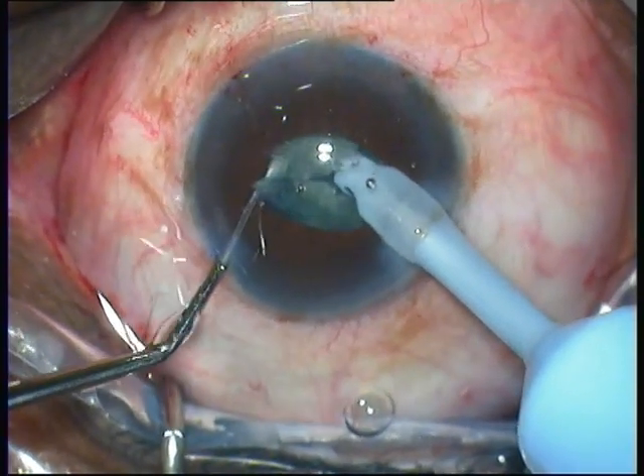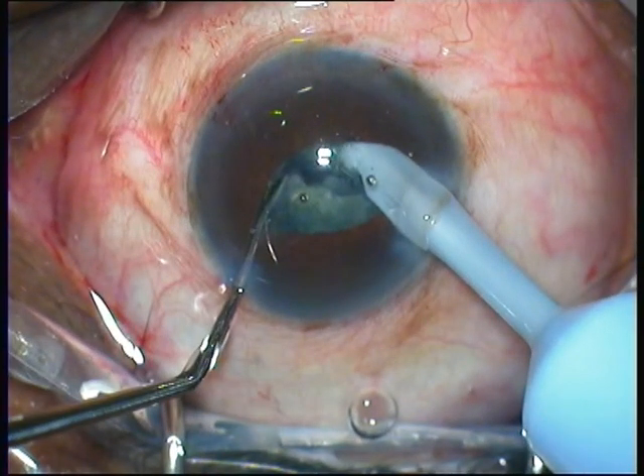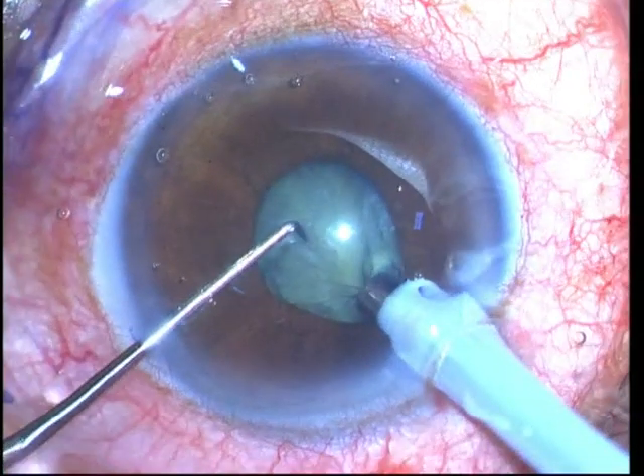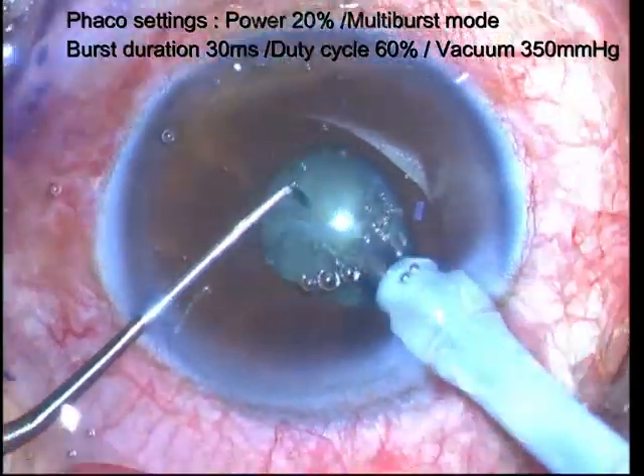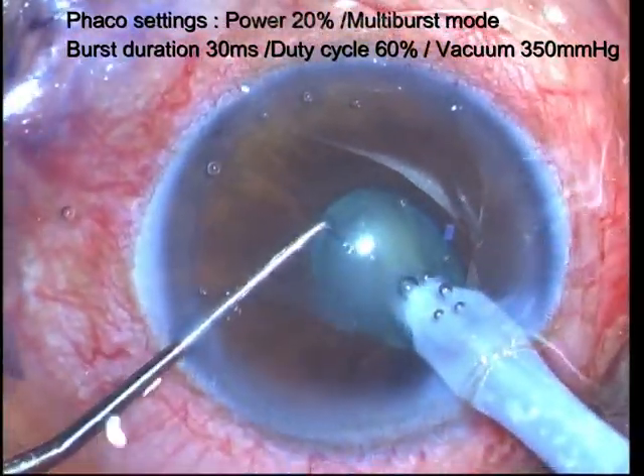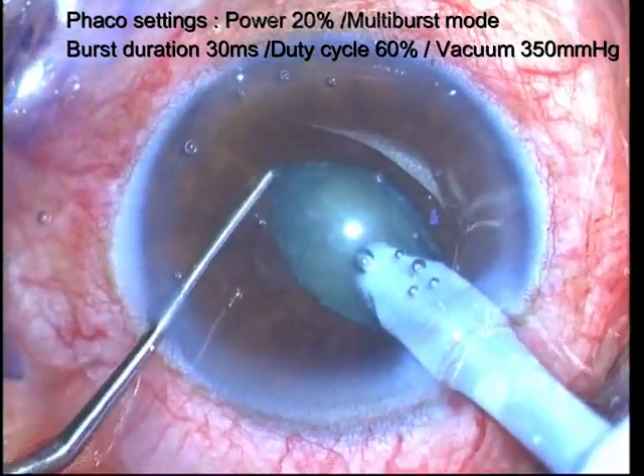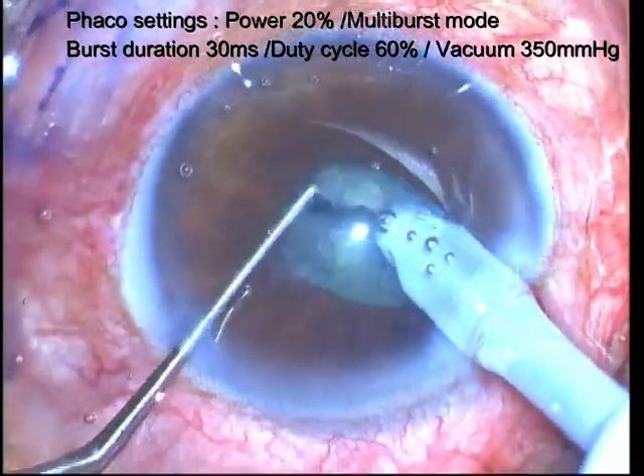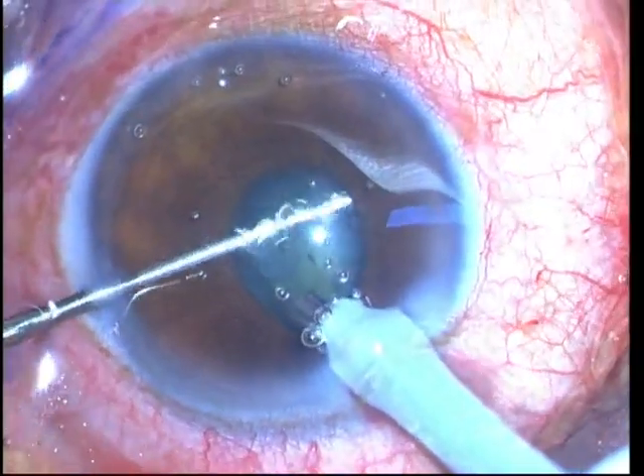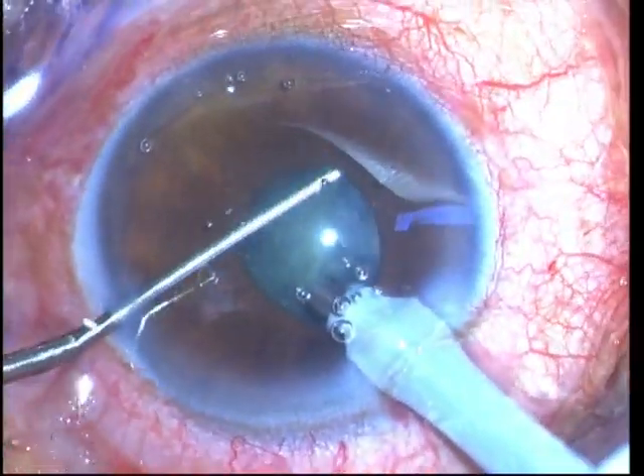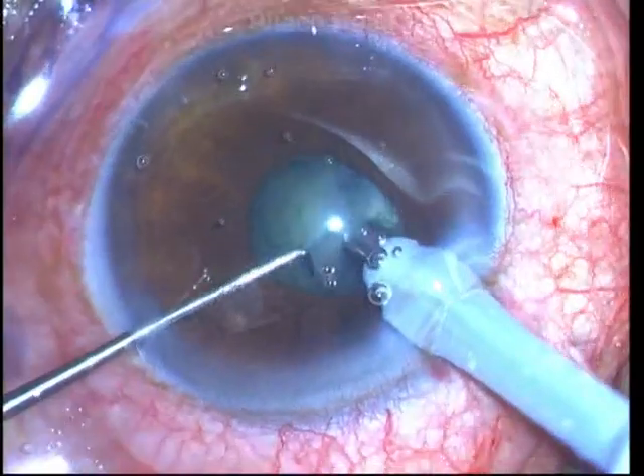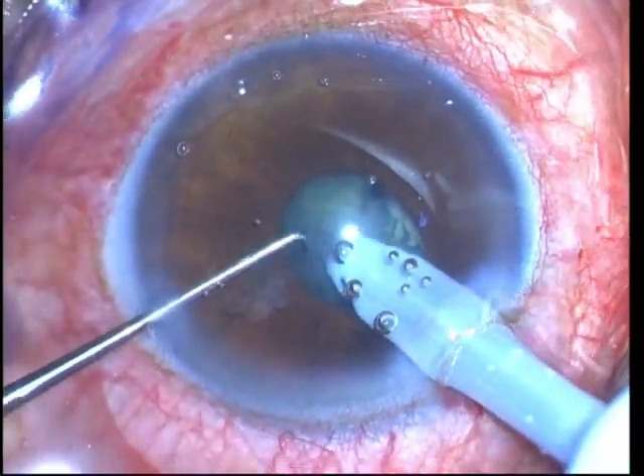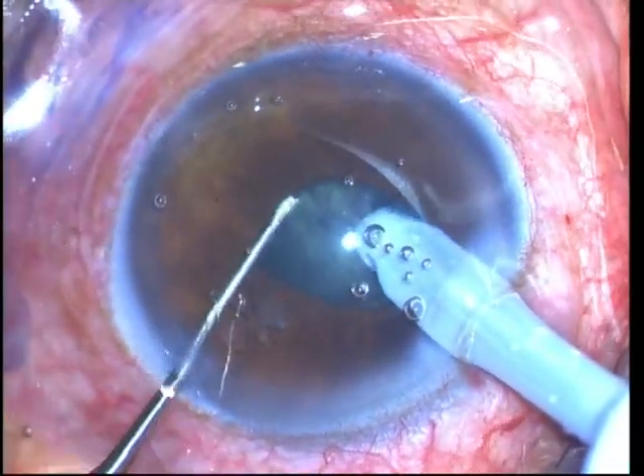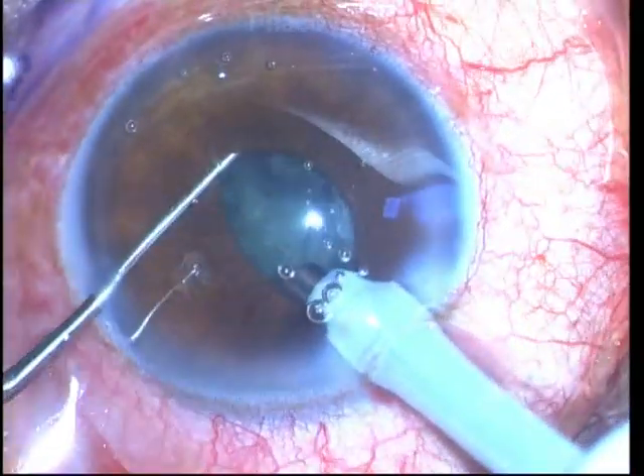Now let's switch over to the Venturi pump and see how the chopping procedure happens. In the Venturi pump, using a vacuum of 350 millimeters of mercury, I'm using burst mode phaco because this is a grade 2 nuclear sclerosis. However, using a very low power of 20% and a burst duration of 30 milliseconds and a duty cycle of 60%. The ease of burying the tip, the holding power, as well as the chopping ability are comparable in both the machines.